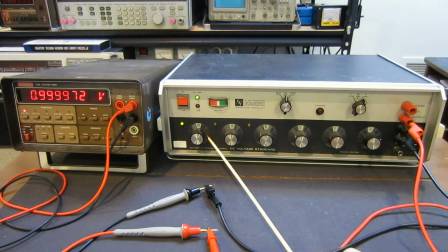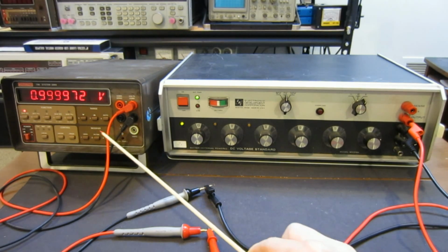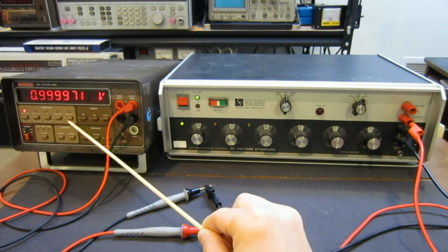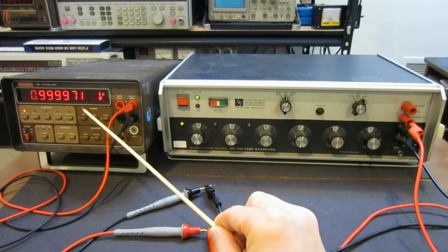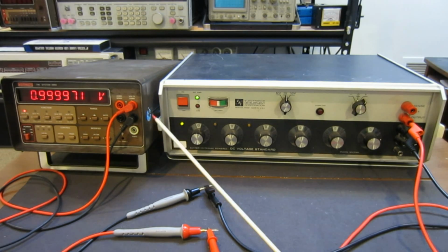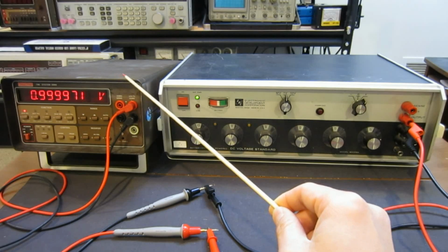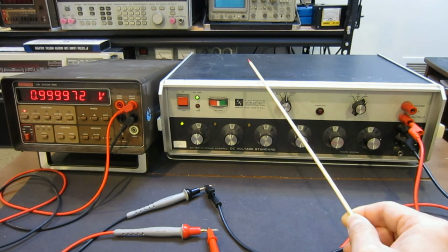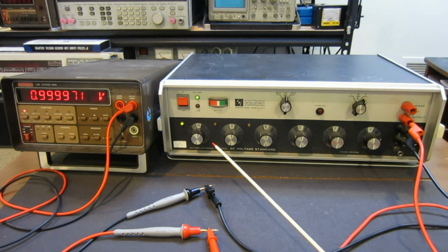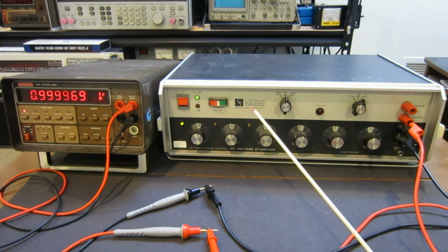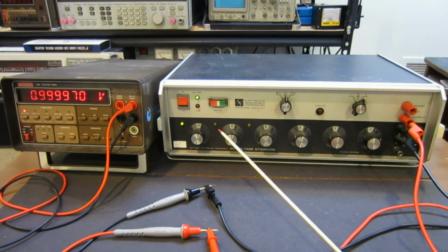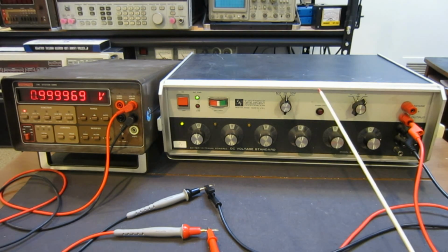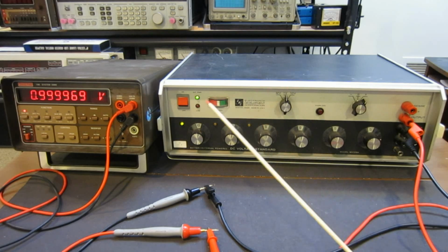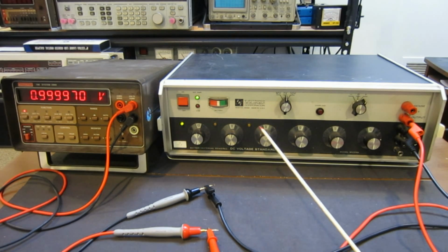Now I'm outputting 1 volt. As you can see on the multimeter, it is fairly stable, reading 0.999971. Of course, this multimeter could be a little bit out of cal, and this thing definitely hasn't been calibrated for a long time. I actually couldn't find a calibration sticker on this unit, so presumably it had been in storage for an extended period of time, at least for the past 10-15 years.